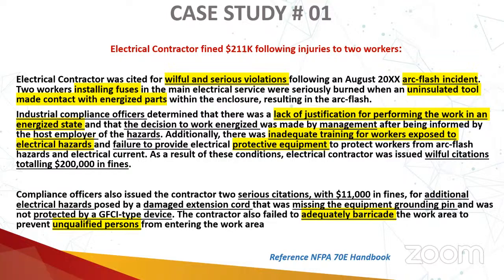So GFCI is not there for protection of circuits. We have overcurrent protection relays. Those overcurrent or short circuit protections are there to protect equipment or enclosures. A ground fault circuit interrupter is a device there to protect human beings. GFCI is for lower levels of current, so it won't protect you against an arc flash. GFCI is there to protect you mostly against electric shock hazard.